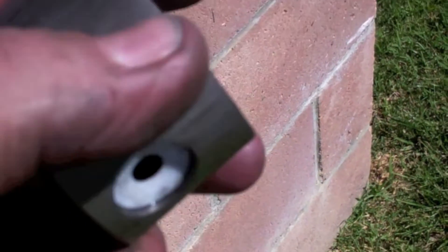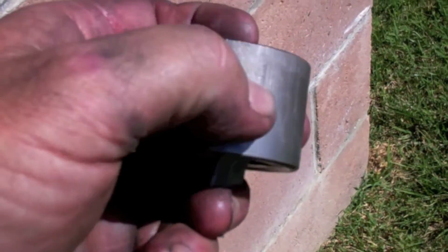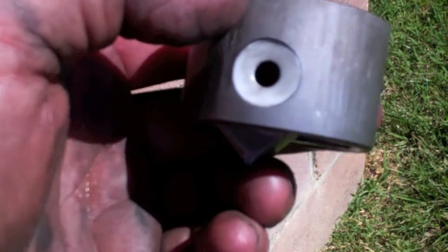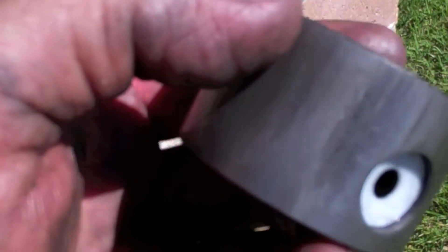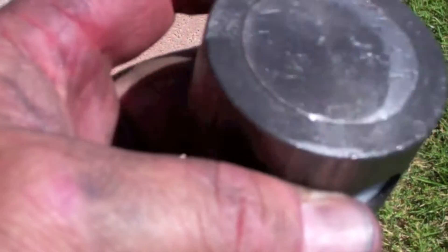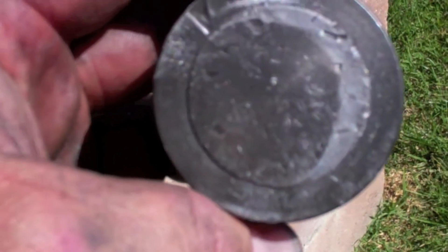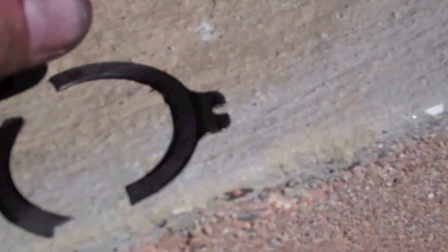Coming back to the compressor. Look at how the scores of the piston walls are. These are rough, like sandpaper. The top is hammered. Just look at the valve plates again. Pretty bad, the crank.